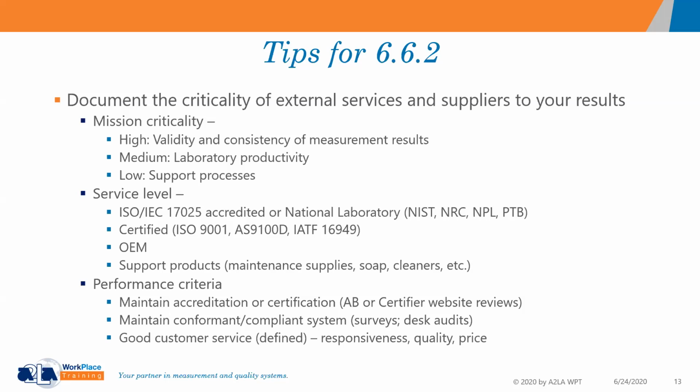Are they still accredited? Maybe you want to do that before you request a new calibration from them, or maybe you just want to do it once a year. Maybe you know that they're a good calibration lab, so you trust them and monitor them less frequently than doing it every time you get a calibration from them. So it's up to you what risk you want to take on for your organization.